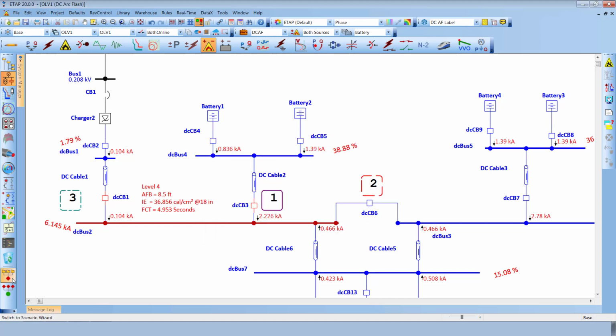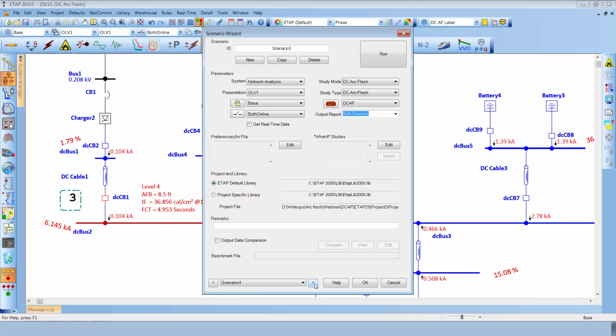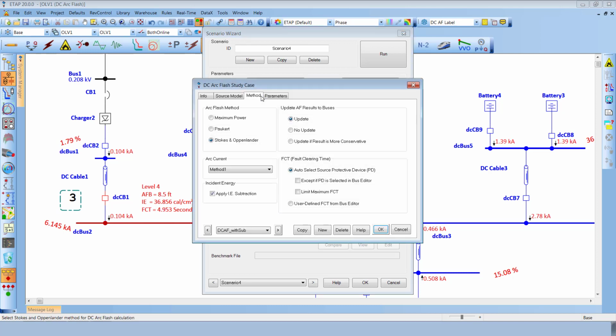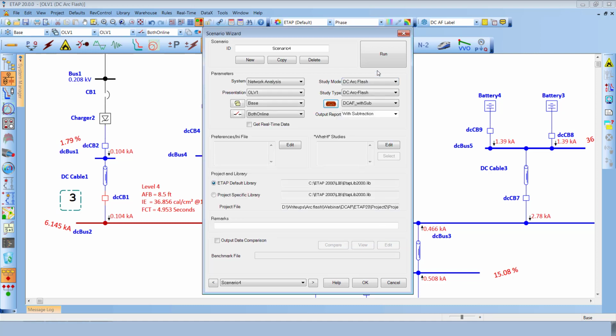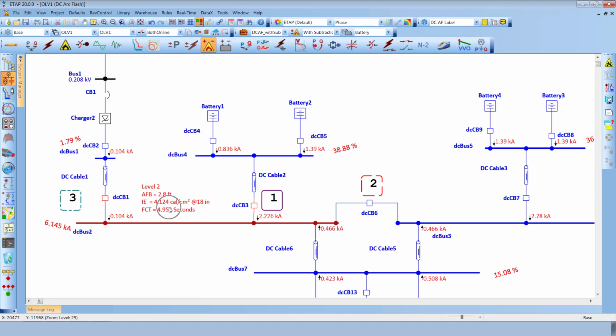Now I made a separate scenario, which is called scenario number 4, which is considering the both online source configuration, which is considered to be the highest incident energy or the worst case, and to see the account of the subtraction included in this particular scenario. Upon running the calculation with subtraction, you can notice the reduction of the incident energy from a category 4, or a level 4, to a level 2 respectively.